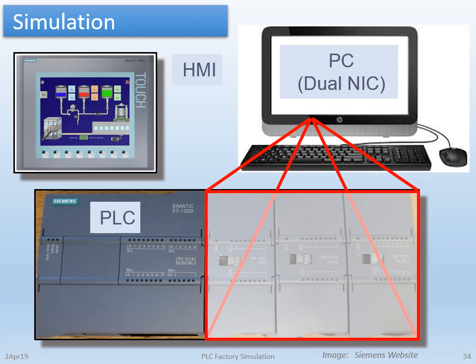As I mentioned previously, the simulation uses a real PLC and real HMI. The only difference here between the simulation and a real environment is that the actual physical IO on the system is not on the PLC itself — the inputs and outputs exist within the environment of the simulation. However, there are two items that should be mentioned: if the simulation and programming via TIA Portal exist on the same PC, dual network interface cards are needed — one for the simulation and one for TIA Portal. The second item is that the IO does not update during the traditional IO scan, but concurrently with the PLC program, similar to an HMI update.